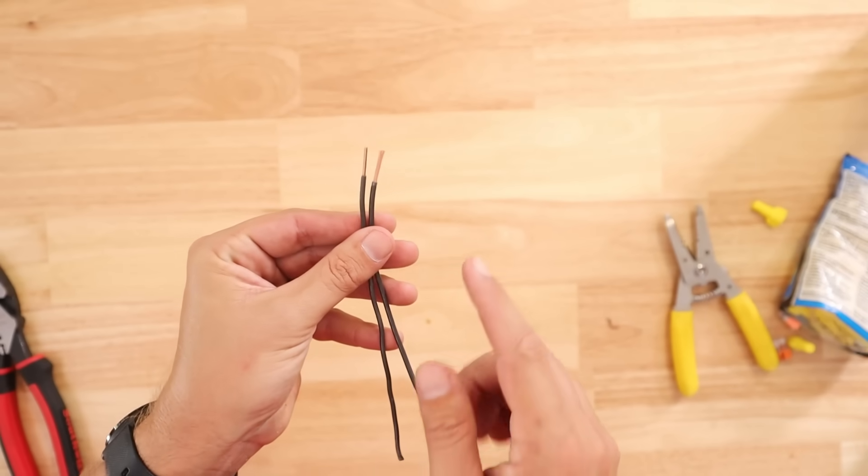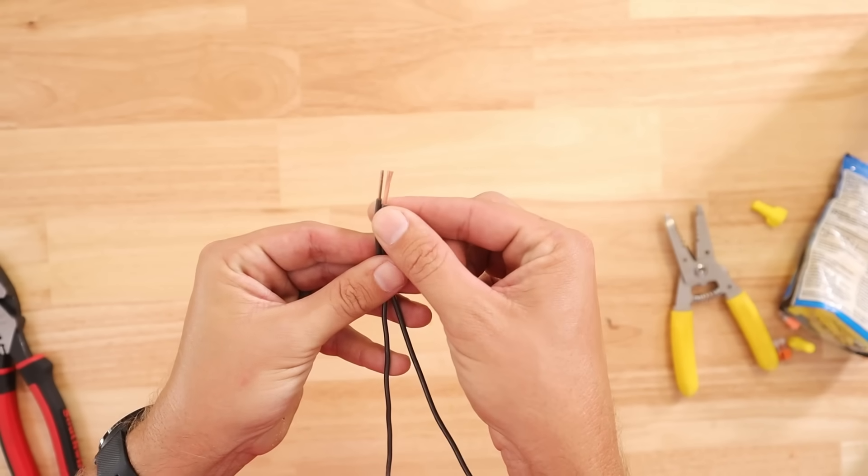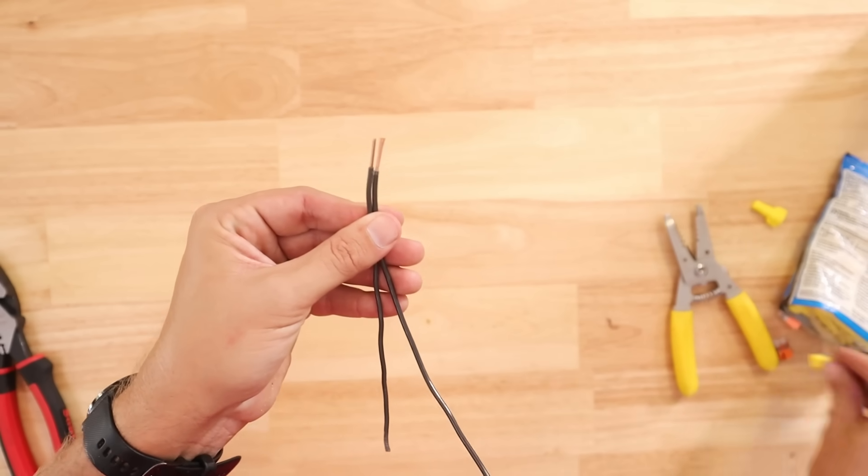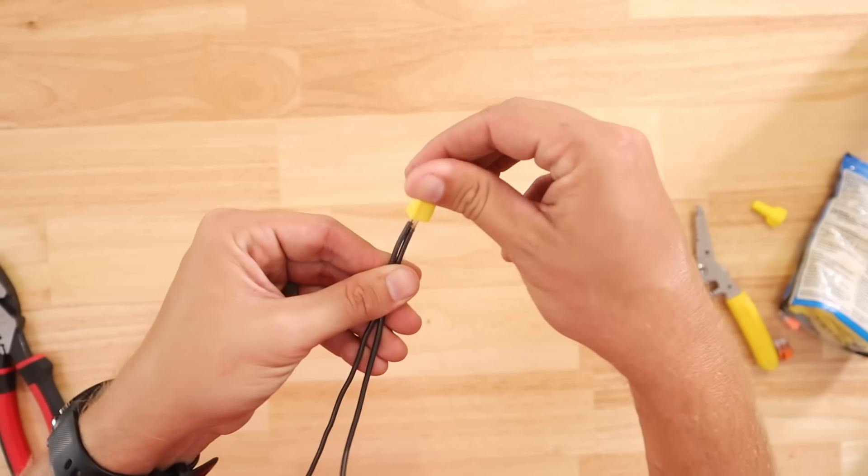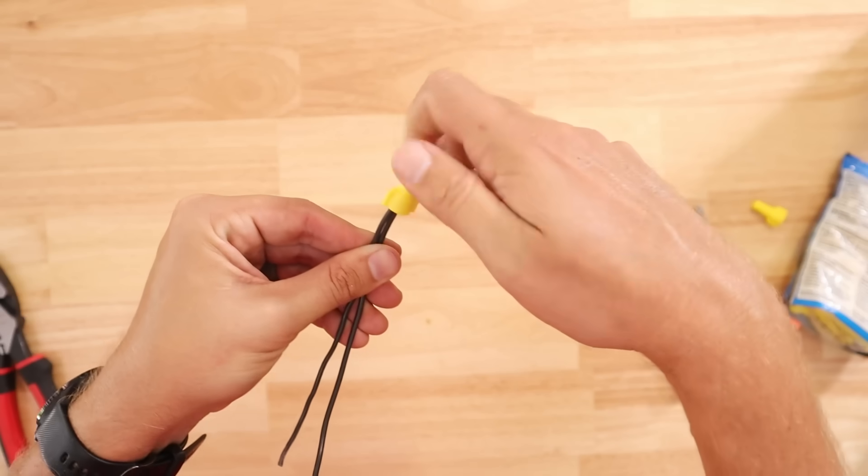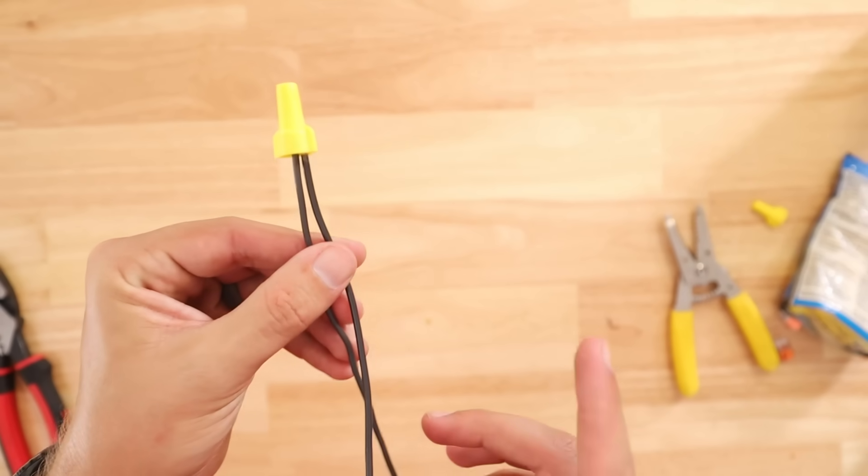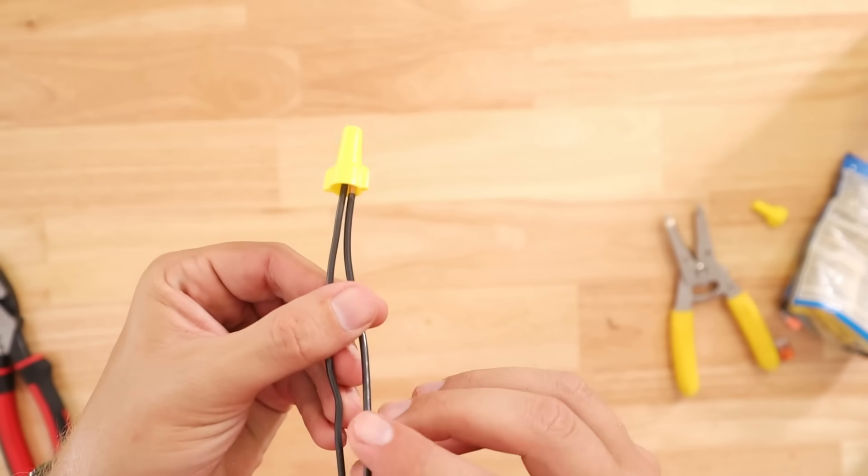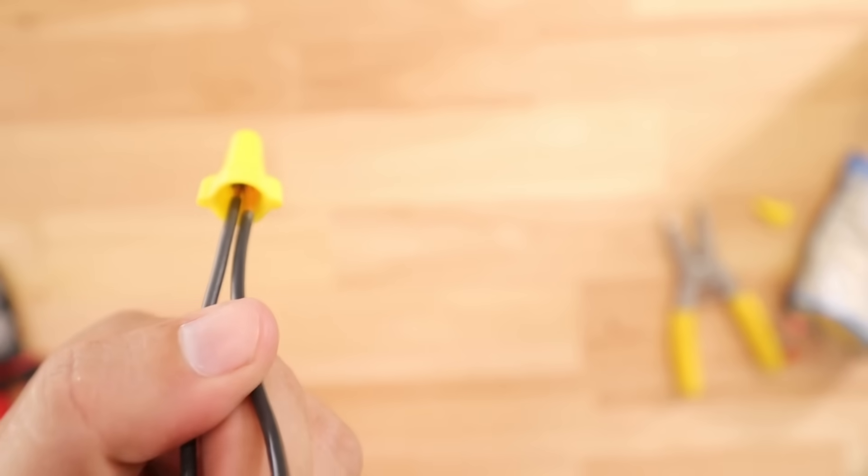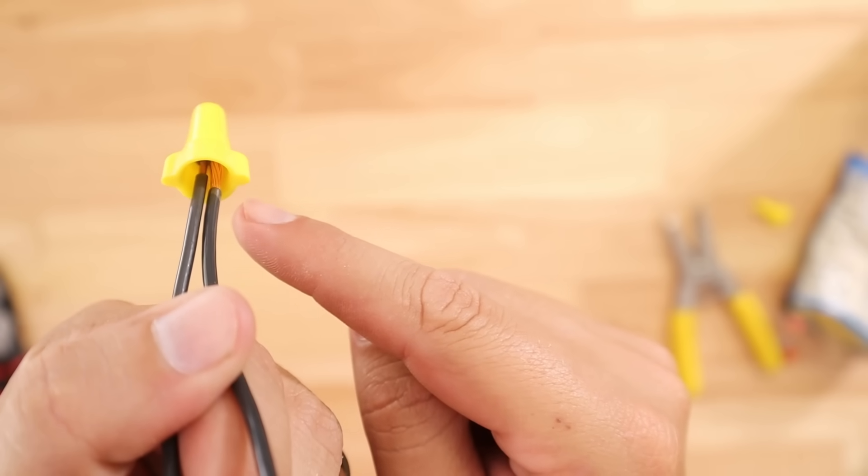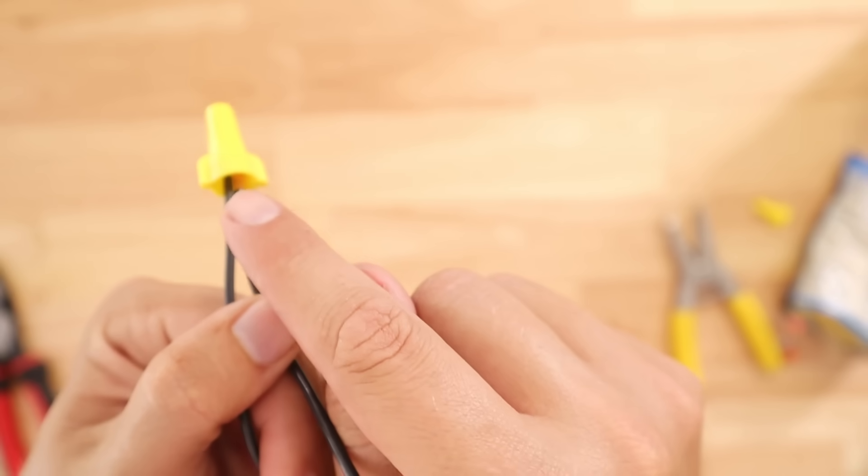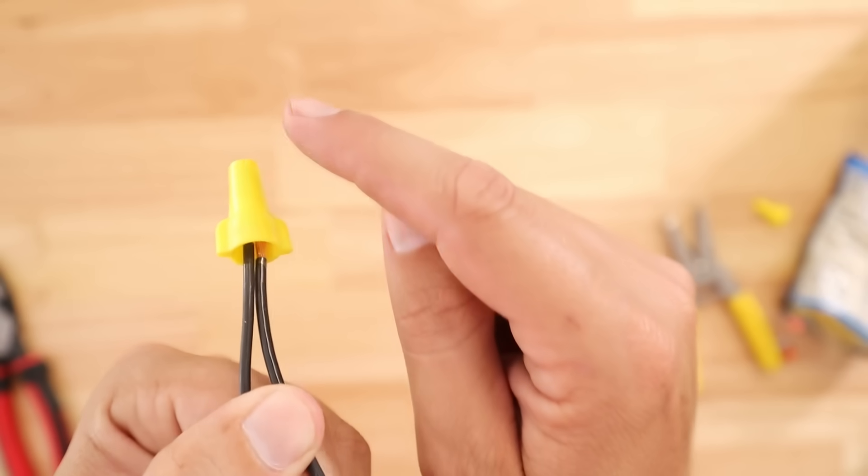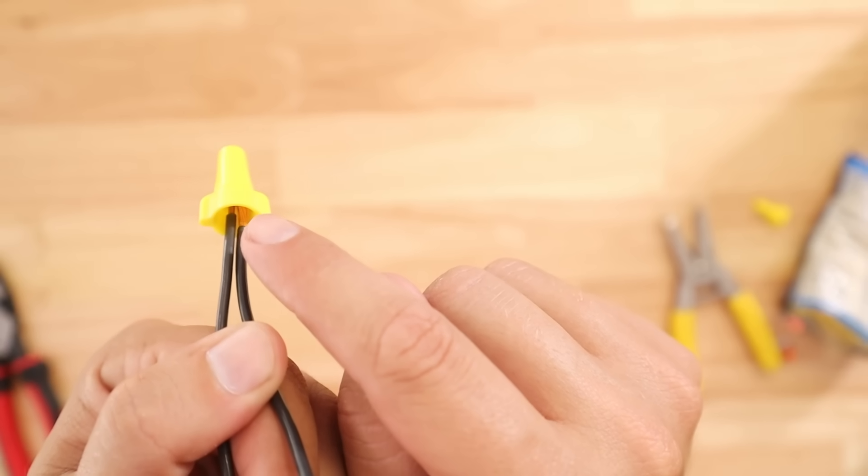Alright so again very similar to the solid core to solid core what people will do is they'll just take their stranded put it up next to their solid core take their wire nut put it underneath of the wire nut and just spin it on. One thing that happens a lot of times when you do it this way and you just put them up next to each other is if you look underneath of this wire nut you can see that the stranded wire actually dropped down from the solid core wire. So we know that the solid core wire is seated higher up in the wire nut than the stranded wire which could point to not having a very good connection.